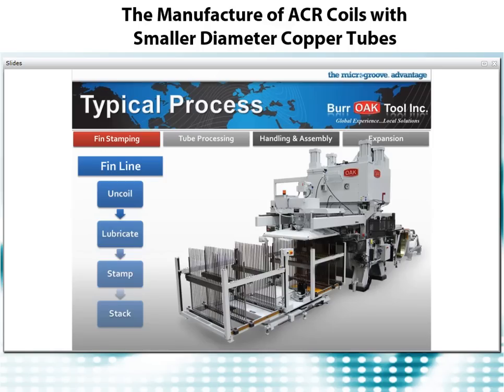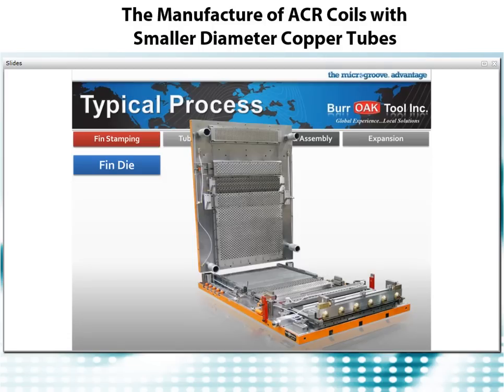The stock comes in various widths depending on the number of rows of the fin die and the tonnage capacity of the press. Our present presses have 30-ton, 60-ton, 100-ton, and 160-ton capacities and can support increasingly wider material. The increasing tonnage reflects increasing capital equipment price, but the real question is the price per hole produced. If high production rates are required, a larger, more expensive press can manufacture fins more efficiently, actually providing a lower total cost per hole. The suction unit provides support for the fin before it reaches its correct length and is cut, and the stacker mechanism collects and maintains cut fins in a vertical stack in preparation for their removal when the stack is complete.